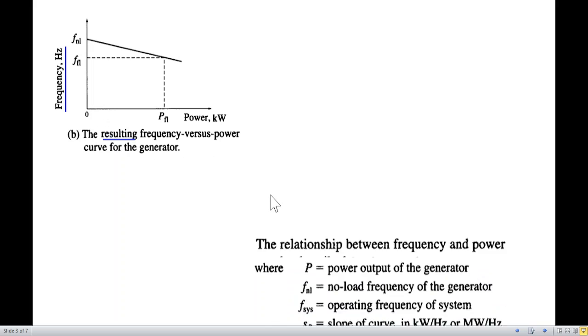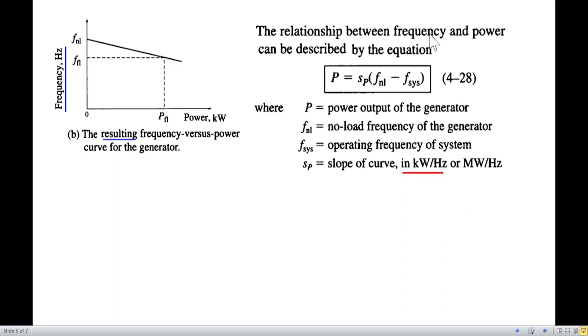In the book, the relation between frequency and power is given by this equation. And this is similar to y equals mx plus c, or y equals mx, the line equation. Here, p is the power output of the generator. No load is the no load frequency. Then f system or f operating is the frequency lower than this. And then the slope of the curve, this curve slope is kilowatt per hertz.